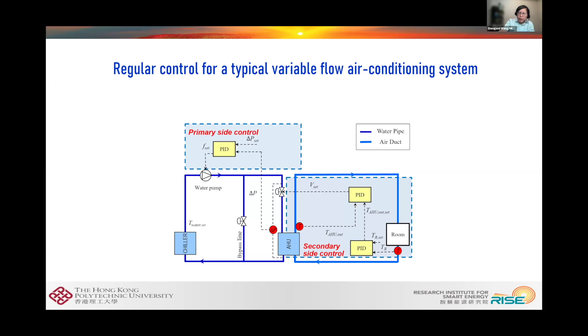In buildings we have many variable speed drives, such as variable speed fans, chillers and pumps. We can control the energy use of those devices to follow the needs of the power grid. We developed strategies to change the power use following the signals, and that was not a big issue.